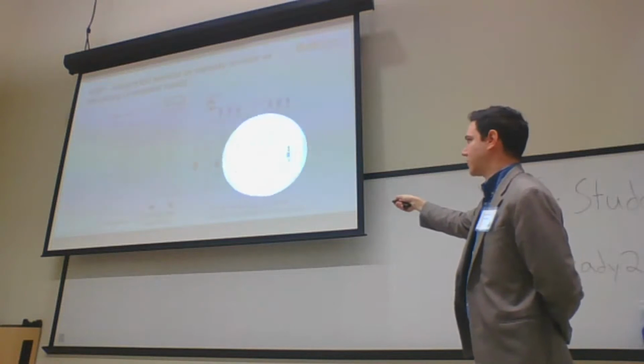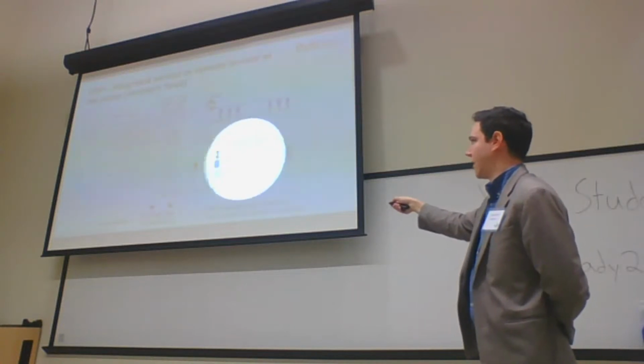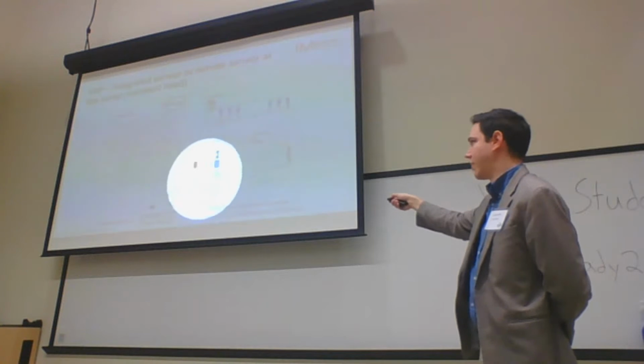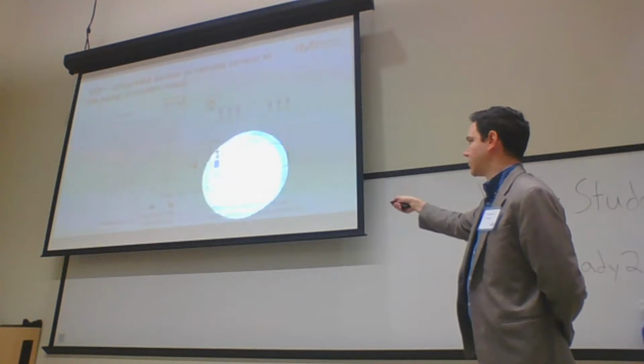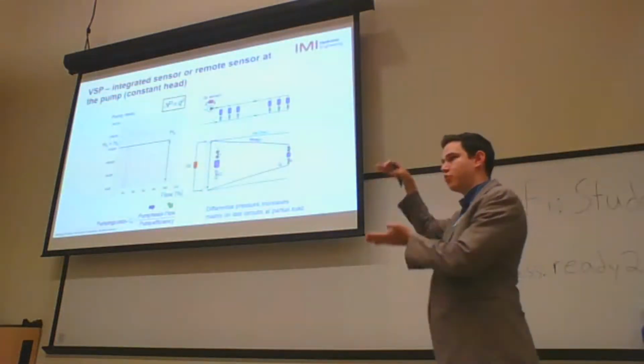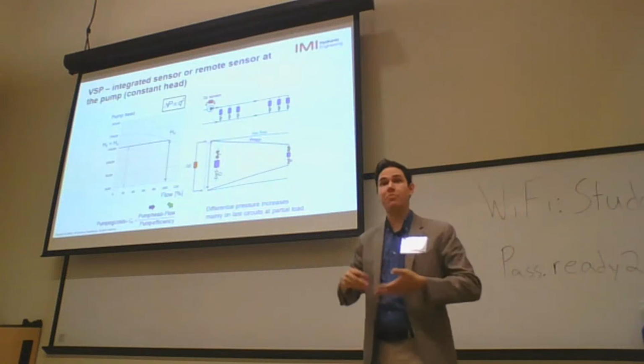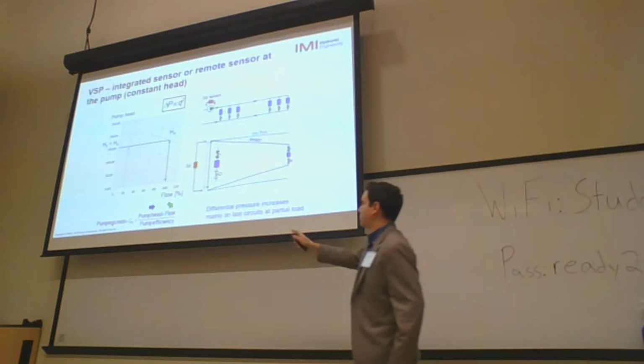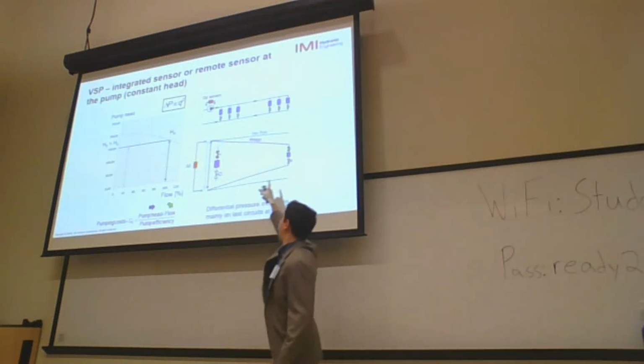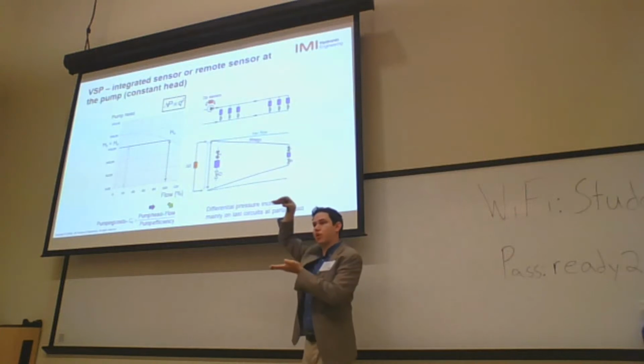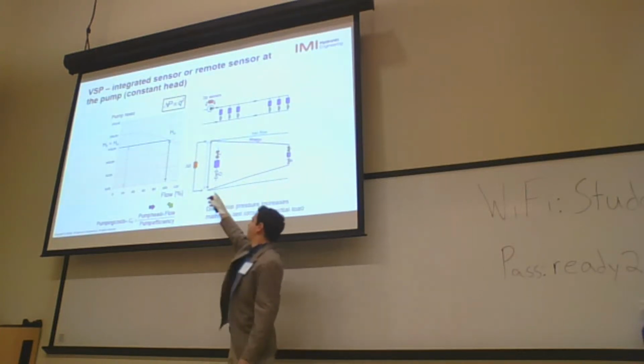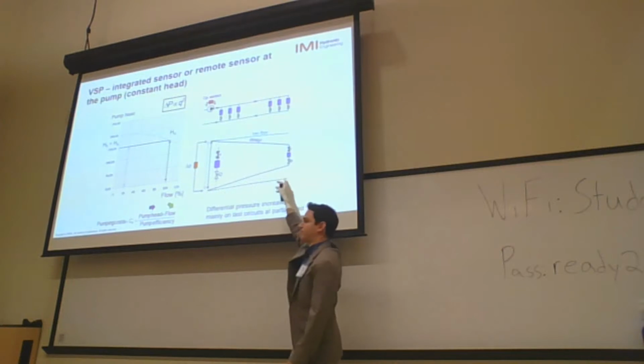looking at this graphic right there at the bottom right. This is what is extremely important for us to understand: my DP sensor is right there, where I have my biggest differential pressure in my system, that is my pump. At the design condition, the two black lines that you see right there are the differential pressure going through my whole system, so all of my pipe pressure drops between my first coil and my index coil. So you have this huge pressure drop going from the first equipment until your last one.